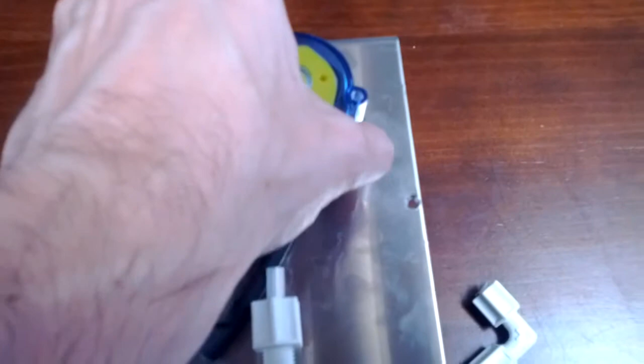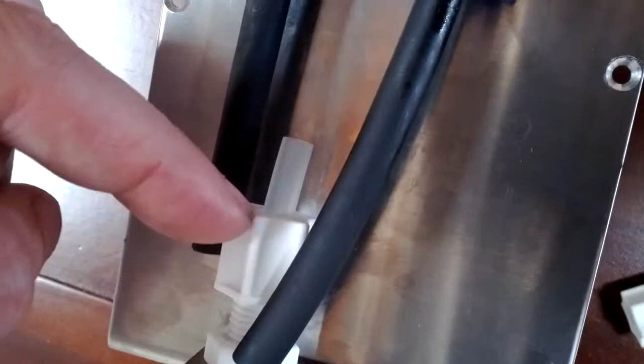The first thing we have to do is cut these neoprene lines to length. Basically you want this black neoprene line to more or less be just past the length of the top of this compression fitting here. What you're ultimately going to do is take this black neoprene line and slip it over this tube, so the idea is you want the neoprene line to end more or less right here, without it being under tension or compression.